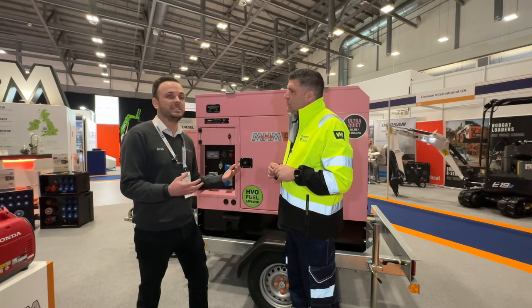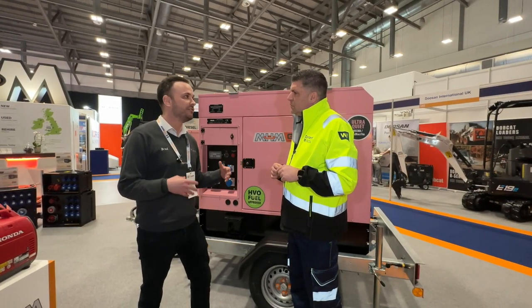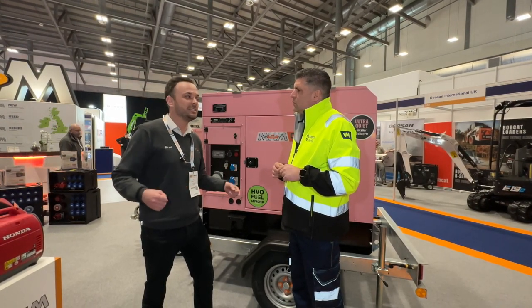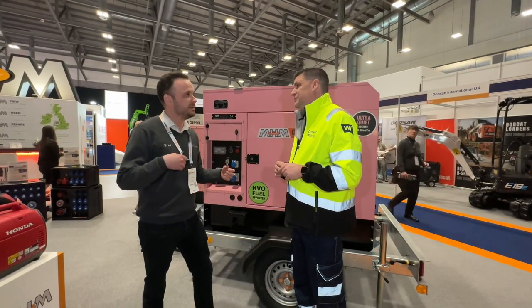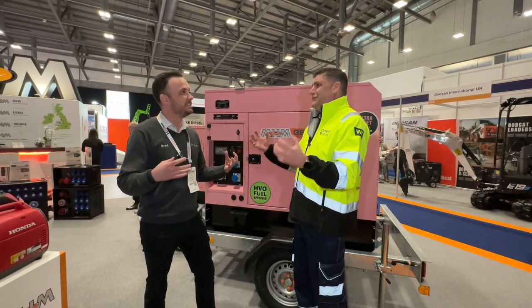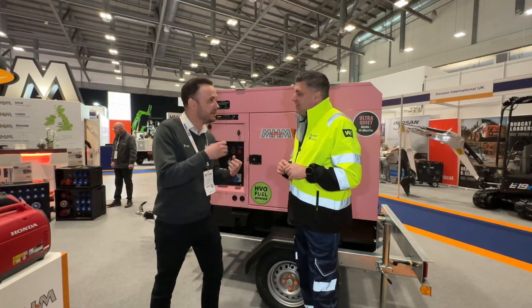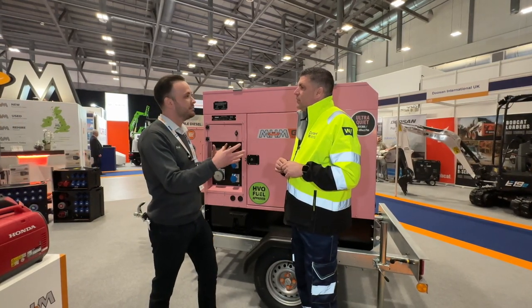What's unique about this machine is it's ultra-silent — only 50 dBa at seven meters. The size is about 10 KVA; it's the first of its kind in this size. Traditionally a 10 KVA is a wheelbarrow-style 3000 RPM machine, really churning and making a lot of noise. This one is 1500 RPM, so it really purrs rather than makes a lot of noise.